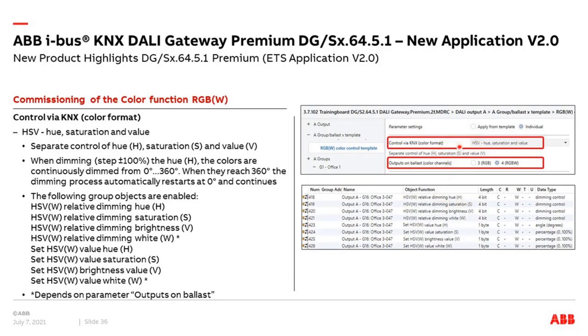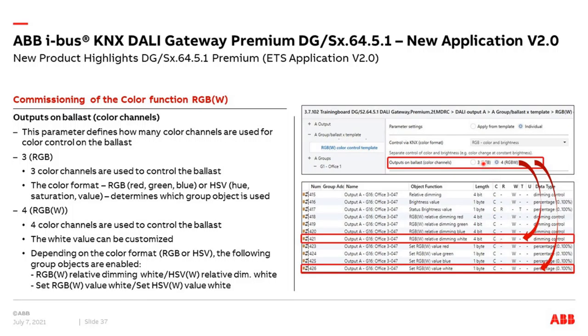If you prefer the HSV color format (hue, saturation, value), you get group objects for relative dimming of saturation, brightness, and white, and for setting values: the hue uses a KNX data point type 'angle' between 0 and 360 degrees, while saturation and brightness are between 0 and 100%. With the next parameter — 'outputs ballast with white or not white' — if you select 'with white' (RGBW, four colors), you additionally get objects for dimming white and setting the white value.